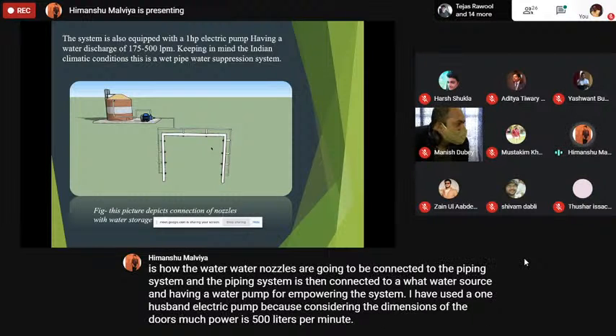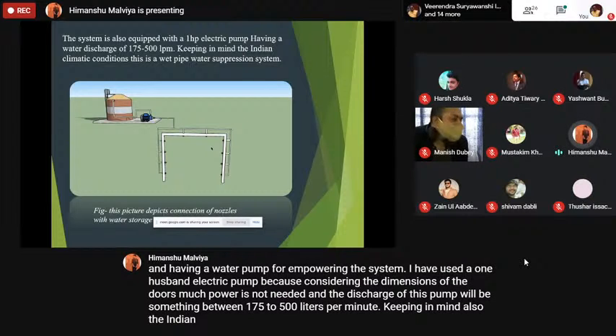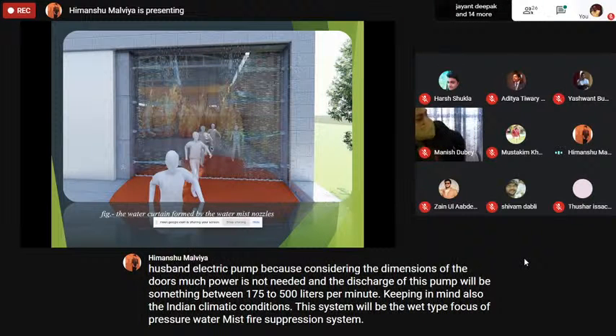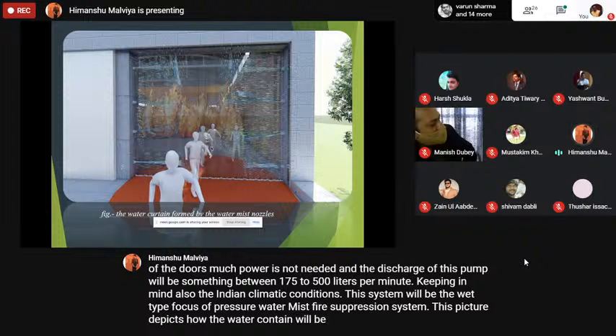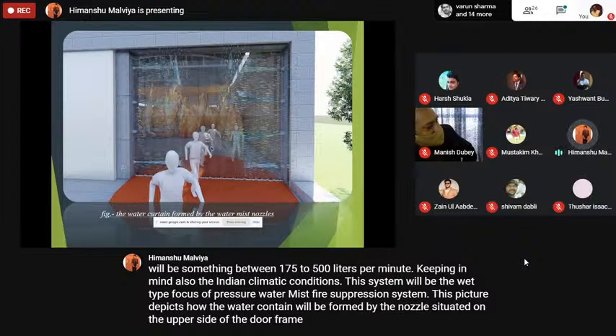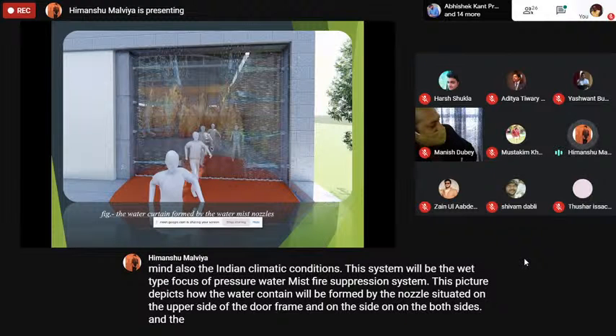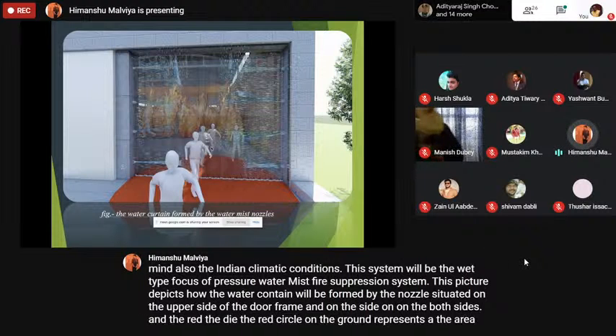Keeping in mind also the Indian climatic conditions, this system will be the wet type water mist fire suppression system. This picture depicts how the water curtain will be formed by the nozzles situated on the upper side of the door frame and on both sides. And the red circle on the ground represents the area where actually the curtain will be formed.